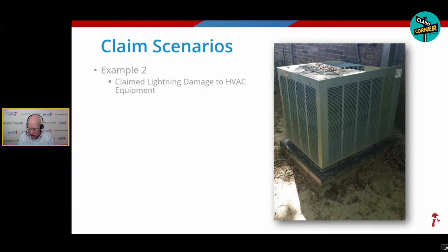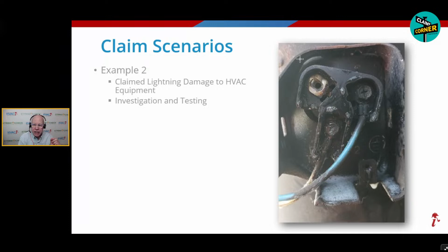Here we got another system. This is looking at the terminals of the compressor, and see that white bubbly stuff? That's refrigerant and refrigerant oil. So we've had a big electrical event inside this compressor. The seal around those are made of glass and they melt at about 470 degrees. So we know we've had a big event. So something's going on. We need more information.